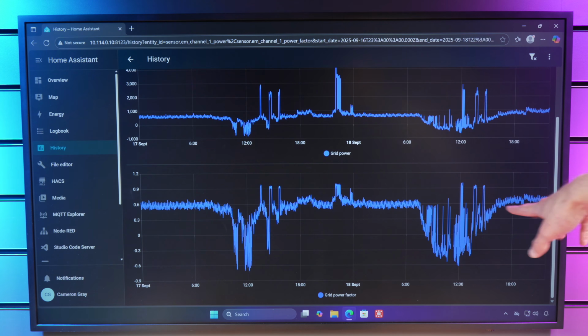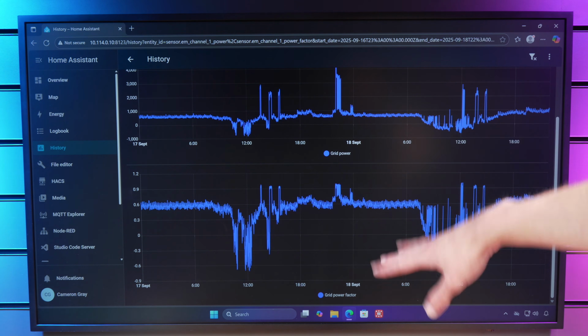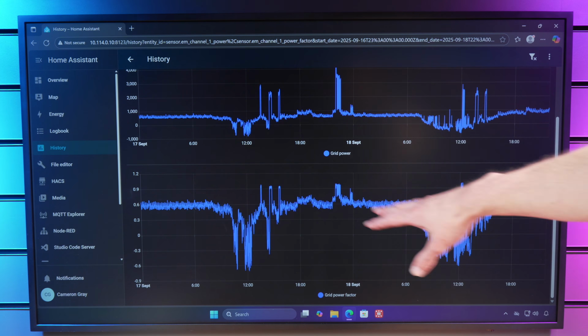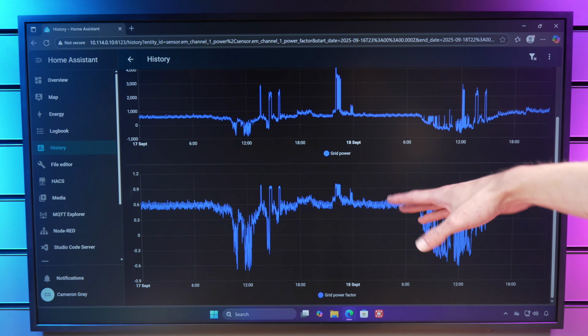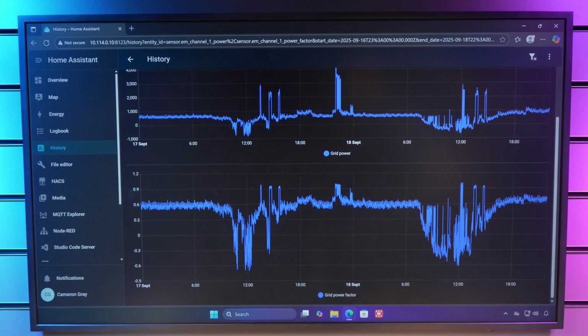And then likewise, adding on the power factor for the grid, we can see that is so much more stable than we were getting before. There's fluctuations there, that's to be expected, but that's completely fine. It's not like before where it was completely spiking up to 1 and basically making no sense at all. However, the solution for this isn't exactly ideal.